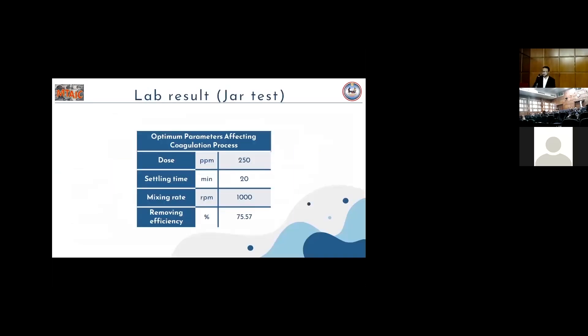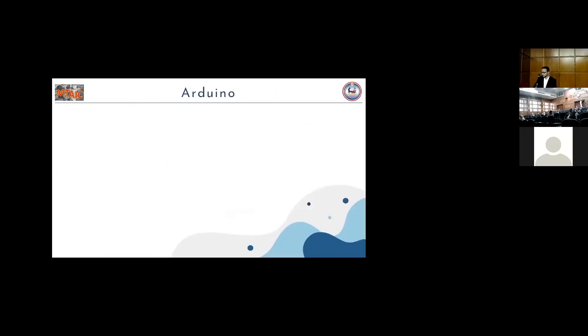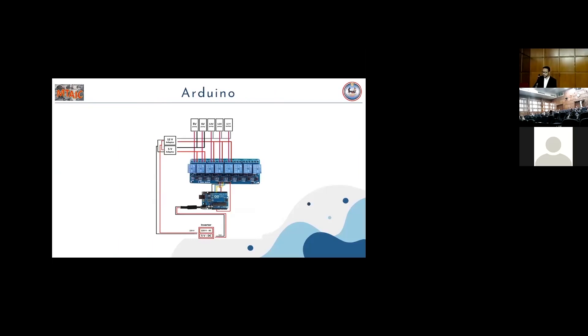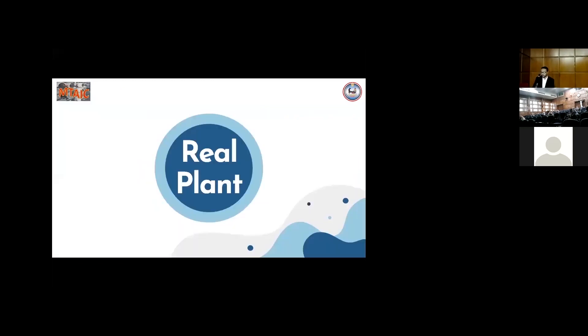The lab results for the optimum conditions in pilot plant for the coagulation process is found to be the dose is 250 ppm alum, and settling time 20 minutes, mixing rate 1000 rpm, with efficiency of turbidity removal 75 percent. The coagulation and flocculation tank was designed to achieve the highest capacity for our pilot plant, to make up for the long-time settling, while maintaining the pilot plant size as small as possible. The Arduino is used to control and operate the pilot plant. And according to this analysis, the real plant will be designed to treat underground water to be used for irrigation.